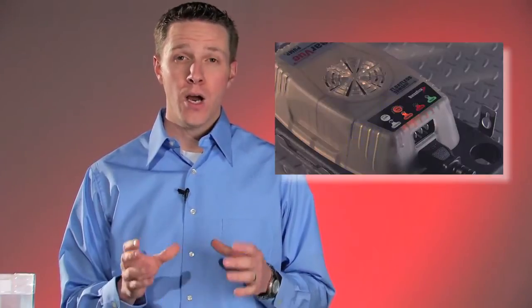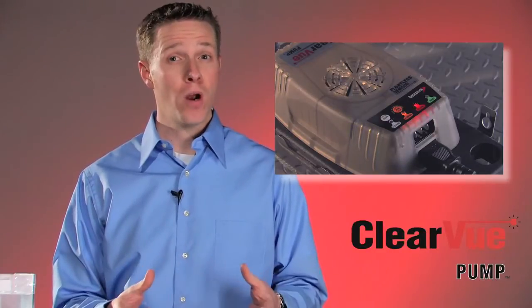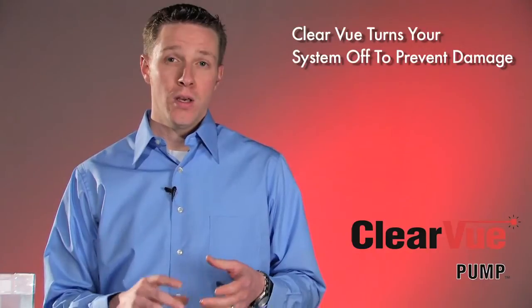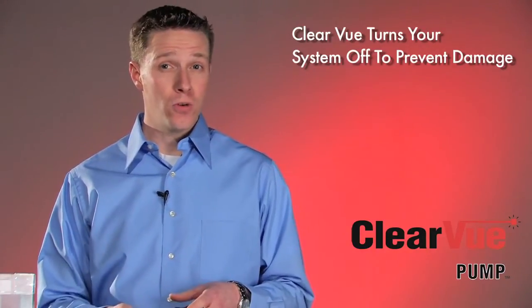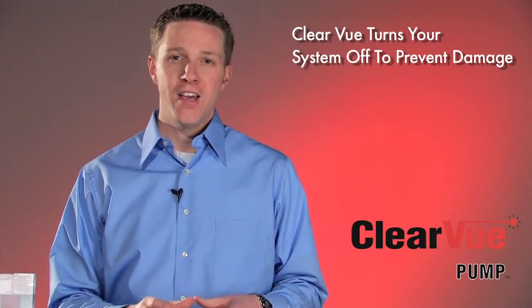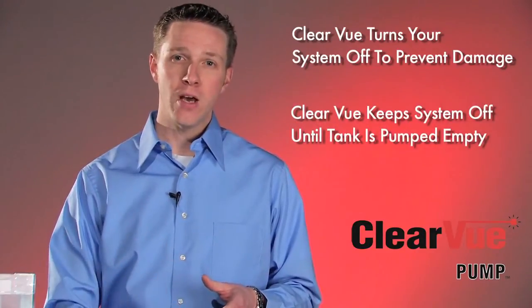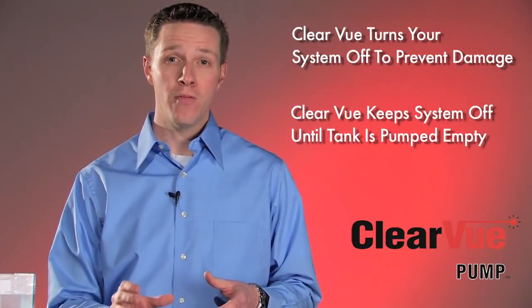While ClearVue is in an alarm condition, a couple of key things are happening. The first thing is that ClearVue, if it's wired into your control circuit, has shut off the compressor, which will prevent an overflow condition or damage to its surroundings. The key difference between ClearVue and a normal condensate pump is that it will keep your compressor shut off until water has pumped down to the bottom of the tank and come off of that empty sensor.